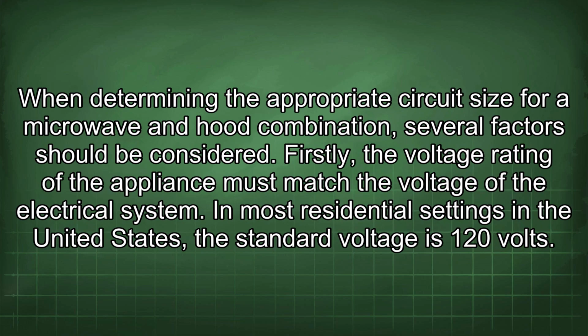When determining the appropriate circuit size for a microwave and hood combination, several factors should be considered. Firstly, the voltage rating of the appliance must match the voltage of the electrical system. In most residential settings in the United States, the standard voltage is 120 volts.